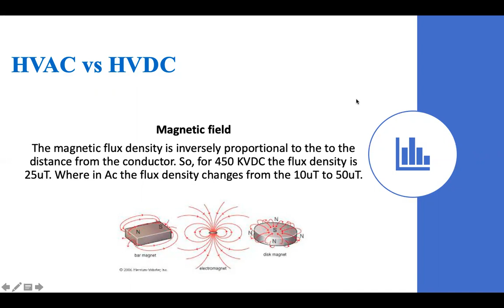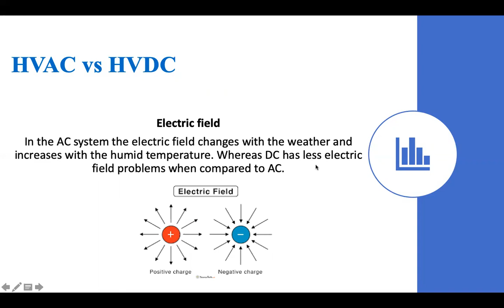The other parameter is electric field. In the AC system, the electric field changes with the weather and increases with humid temperature, whereas DC has fewer electric field problems when compared to AC. Corona effect. There is a corona effect which produces hissing noise and has other disadvantages. As we can see in this picture, it is violet blue in color, and there are hissing noises in these high voltage transmission lines. Corona depends on the electric field, atmosphere, diameter, and surface characteristics, but it is very low in HVDC lines.